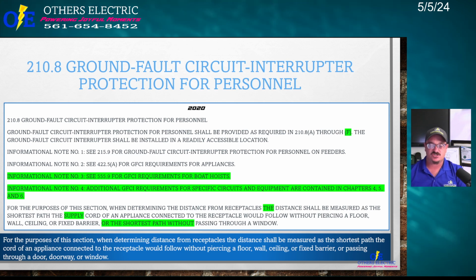They just clarified how to make that measurement, and they also added the shortest path without passing through a window. So let's say, they used to do it all the time, you got an enclosed Florida porch or Florida room, and the kitchen used to be on one side, and the Florida room on the other, and they used to have windows, right? The Florida room's all enclosed, so it's considered indoor. If you have an outlet on the other side of that window in the kitchen, it doesn't have to be GFI protected because they excluded passing through a window. So if you're making that measurement through a window and the other side of that window isn't already a required GFI location, then it doesn't count. So that's the major change there, how they measure the distance.